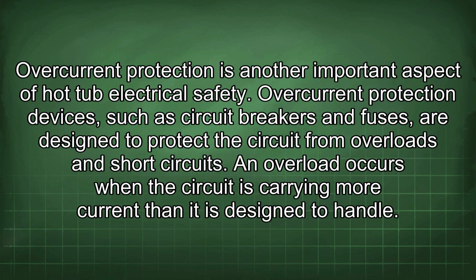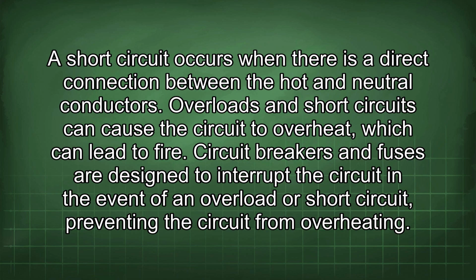Overcurrent protection is another important aspect of hot tub electrical safety. Overcurrent protection devices, such as circuit breakers and fuses, are designed to protect the circuit from overloads and short circuits. An overload occurs when the circuit is carrying more current than it is designed to handle. A short circuit occurs when there is a direct connection between the hot and neutral conductors. Overloads and short circuits can cause the circuit to overheat, which can lead to fire.